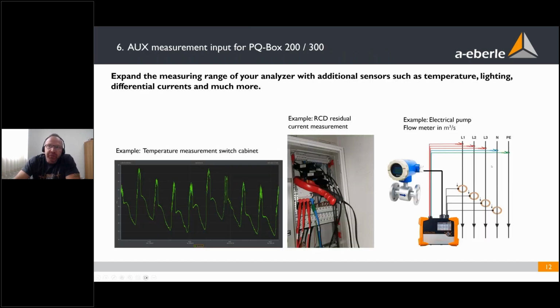All our analyzers measure 4 times current and 4 times voltage, but sometimes I need to measure other signals parallel to the power quality. So sometimes it makes sense that I measure the temperature in a cabinet parallel to the power quality. Maybe some components are getting problems with heat and not with the power quality. Or I measure the load of a transformer and also the heat of a transformer parallel with one measurement. Or at the aux input, I connect a differential current clamp and I measure at an RCD the residual current, and I also can trigger on the current and find out when the RCD is tripping.